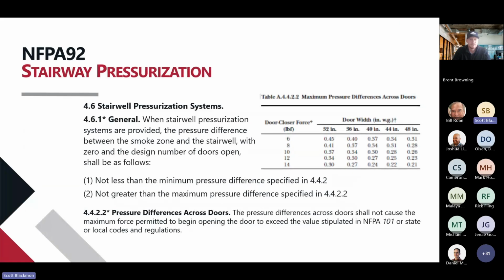And the reason we worry about pressure is we need to be aware that if we put too little pressure in there, we can't keep the smoke out. But if we put too much pressure into the system, we can get to where we can't open doors. So in this case, this little chart right here shows we want to size our systems for about 0.1, 0.12 inches of pressure. You can keep smoke out at 0.05, but you don't want to go above 0.3. And the real reason for that is if you've got a 14-pound door closer with a 32-inch door, if you go much above 0.3, you're going to fail the door pull test. So the door's going to feel like it's locked when you try to push on it. So we want to keep it right around that 0.1, 0.12 when we're sizing these.